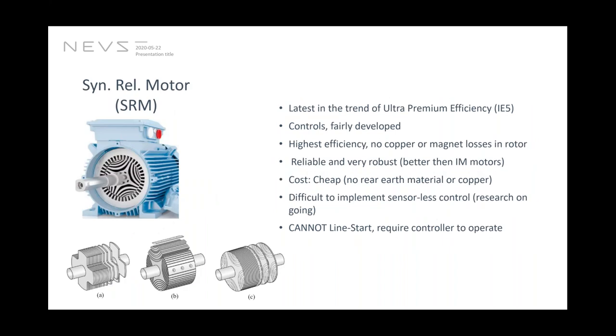The next type is a synchronous reluctance machine, and this is the latest trend in ultra premium efficiency. I think for IE5, this is the only motor that qualifies for IE5. ABB has claimed to have an IE5 standard synchronous reluctance motor. It's quite a difficult thing to achieve IE5 level. Controls are not very well developed, but fairly developed, and if they're marketing it, then obviously it must have good control then. High efficiency, no copper loss or magnet loss in the rotor, quite reliable because you do not have any conductor or losses in the conductor in the rotor. When you're comparing to induction machine, there is no chance of those conductor failures due to overheating.